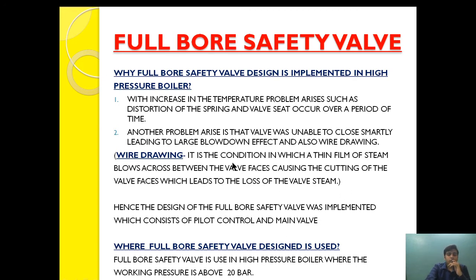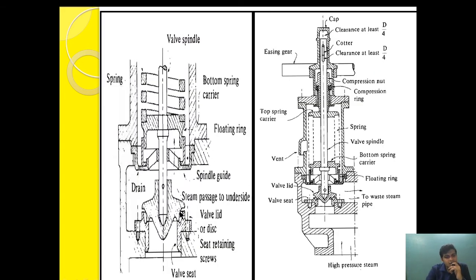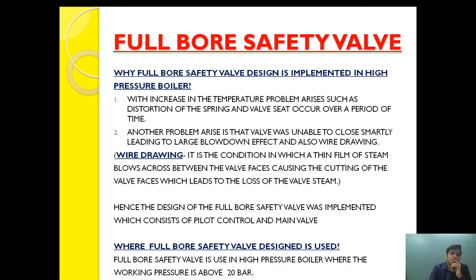This problem was overcome by the full bore safety valve. Another problem was wire drawing. Wire drawing is a condition in which a thin film of steam blows across between the valve face and causes cutting of the valve face, which leads to loss of steam. During the blowdown effect, as the valve was seating, a thin film of steam was continuously escaping. When the valve was finally moving to the closed position, this steam was acting like a wire, causing cutting on the valve surface and reducing the efficiency of the valve.